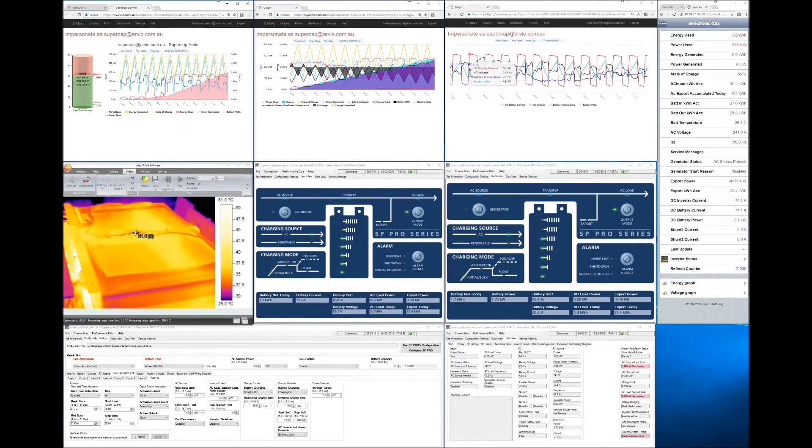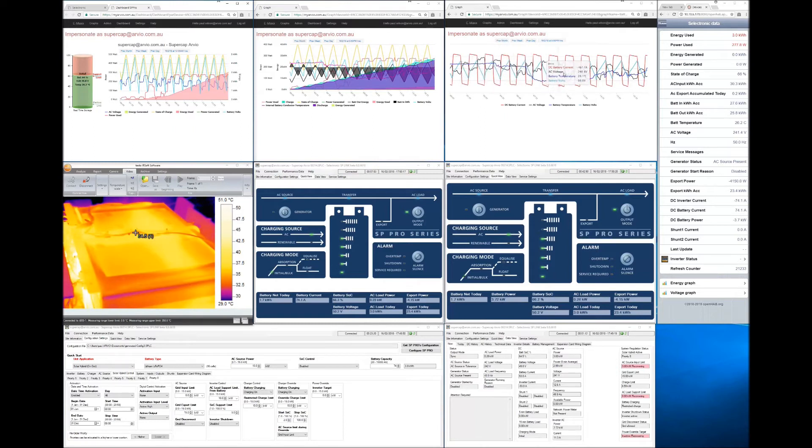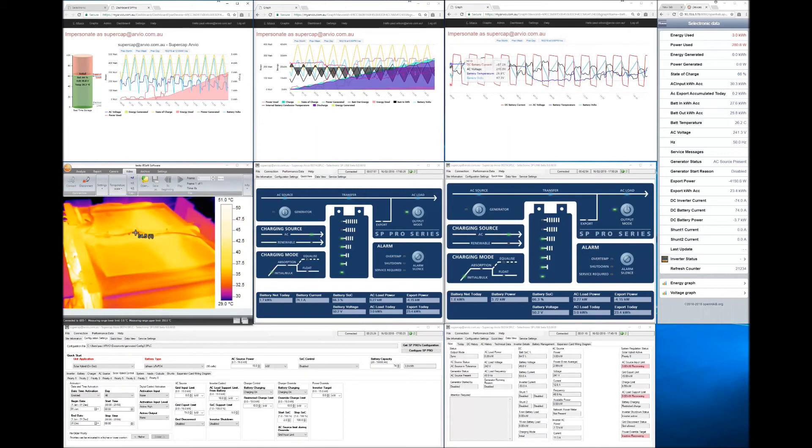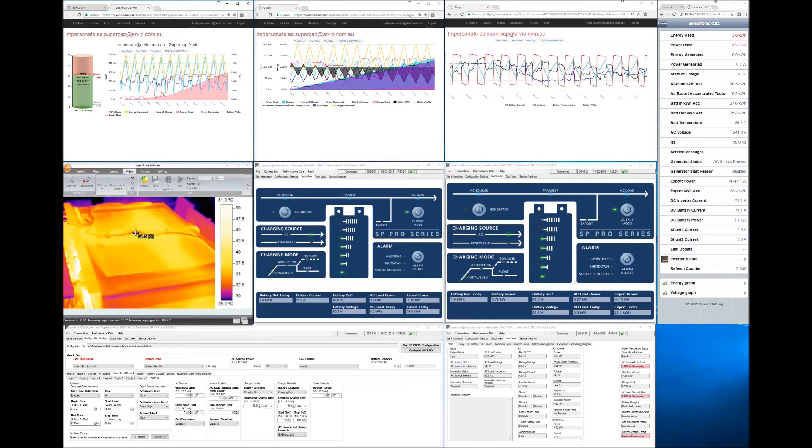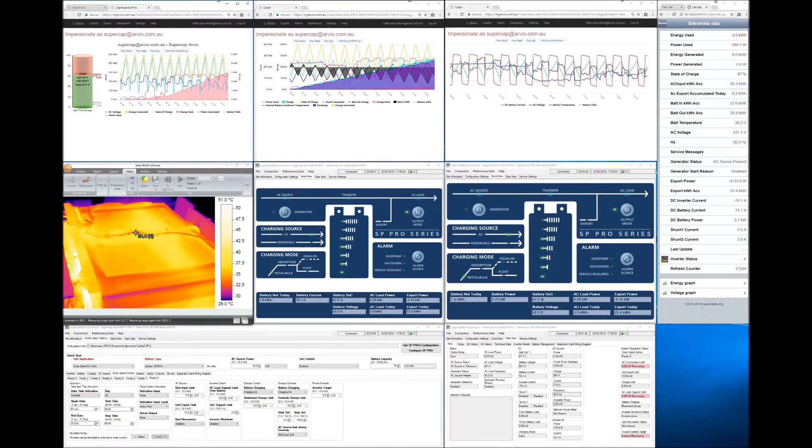Over on the right over here while those changes are happening you can see the battery temperature and the other values. You can see the grid voltage changes over time as well as we export and import. So let's go back down to here again we've got 74 amp charge right now. So here we have a charging source AC and its initial bulk so it's now putting 74 amps into the supercapacitor battery. And that means that it's running at 3.7 kilowatts charge rate. Now it's a 3.55 kilowatt hour total available energy supercapacitor which means it's charging faster than one hour.